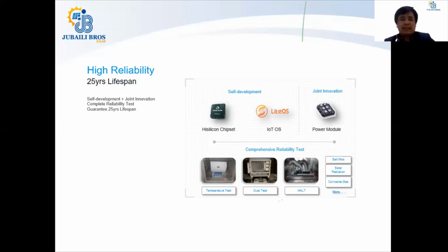Huawei does comprehensive reliability testing such as the temperature test, dust test, HALT test, salt mist, solar radiation, corrosive test, and a few others. In these tests, I would like to give you a quick highlight about the HALT test, which is actually a highly accelerated life test of the inverter.